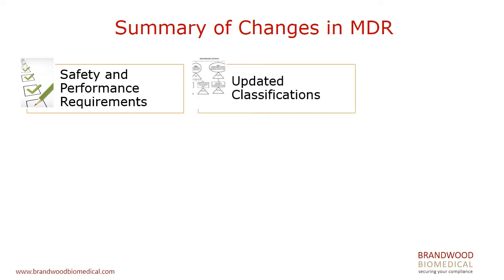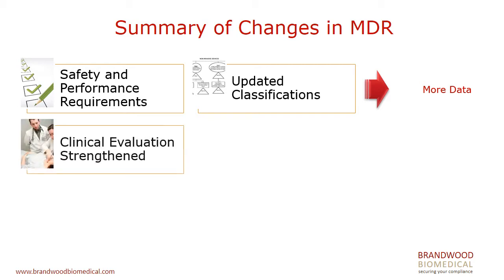We have updated classifications, which have caused some devices to move into new classifications. Mainly, devices are up-classified, with a range of new Class 3 devices and a few other clarifications; not much has moved down. That means more data - more information required to meet the safety and performance requirements, and more devices are going to be at a higher level with a higher expectation for data.